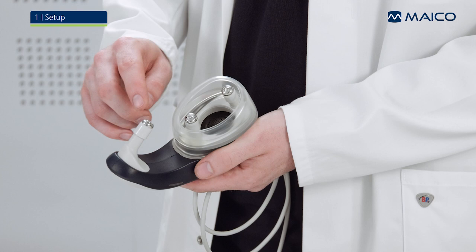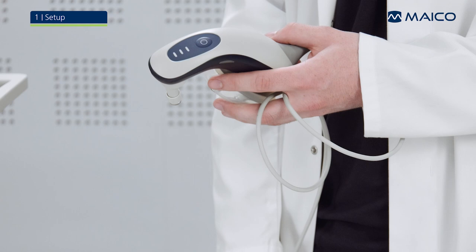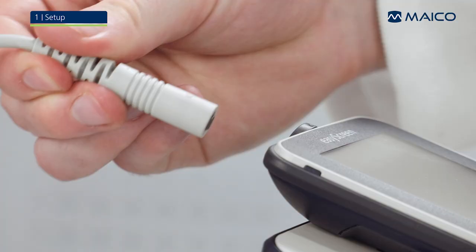This video will show you how to perform an ABR screening using the MAICO EasyScreen and the new BERAphone. The Baraphone is equipped with three measurement electrodes, the ear cushion, two left and right indication LEDs, three status LEDs, and the user control button. To connect the BERAphone to the EasyScreen, search for the dots on the connector and push the plug straight into the socket.